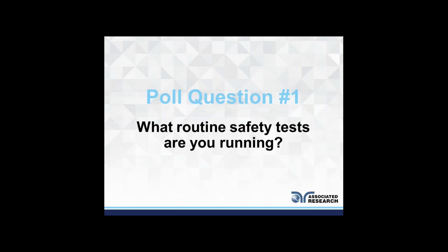So if you had a product rated for 120 volts, you're testing this product at almost 1240 volts, or the voltage listed in the standards, to ensure that if there were any transient voltage coming into the power line, the product is able to handle it, and it would not break down and cause any kind of electrical shock situation.